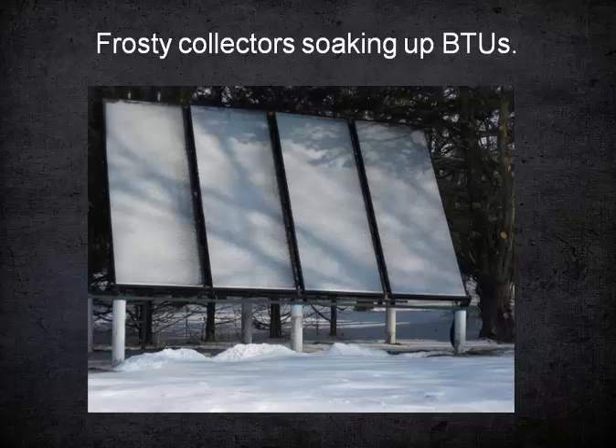To clarify something Colin just said, he doesn't have one single fluid system. The thermal battery in his case is the drain-back tank, and the solar collectors do receive the straight water that's in the battery. But like other systems, to be latent capable and able to freeze the battery, he does have an internal heat exchanger in the tank that's freeze-protected, on a closed loop that goes through the heat pump. I just want to clarify that in case anyone misunderstood and thought all the fluid was the same. It's not -- there's freeze-protected glycol, and there's also just plain water.